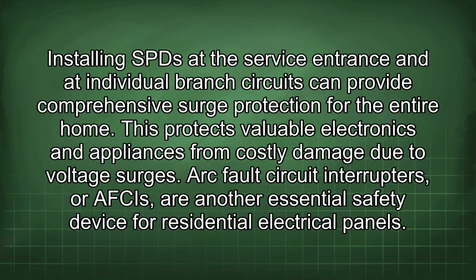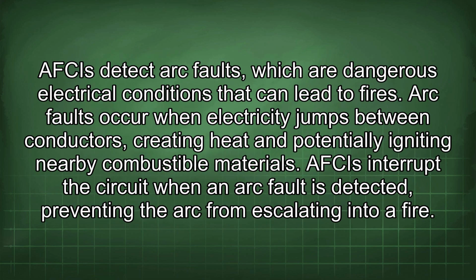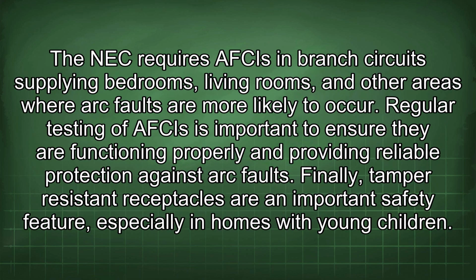Arc fault circuit interrupters, or AFCIs, are another essential safety device for residential electrical panels. AFCIs detect arc faults, which are dangerous electrical conditions that can lead to fires. Arc faults occur when electricity jumps between conductors, creating heat and potentially igniting nearby combustible materials. AFCIs interrupt the circuit when an arc fault is detected, preventing the arc from escalating into a fire. The NEC requires AFCIs in branch circuits supplying bedrooms, living rooms, and other areas where arc faults are more likely to occur. Regular testing of AFCIs is important to ensure they are functioning properly and providing reliable protection against arc faults.